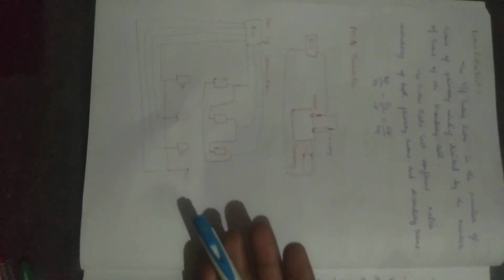Now we are going to check the turns ratio testing. The turns ratio testing is nothing but the simplest form of our voltage ratio testing. With the voltage ratio testing, we are not able to check its accuracy, because there may be load disturbances. We can get a deviation in the injected voltage due to load disturbances, or if any non-linear load is connected to your three phase supply, which can affect the injected voltage of your voltage ratio testing.